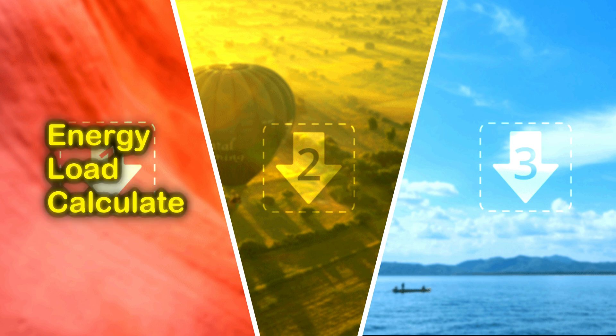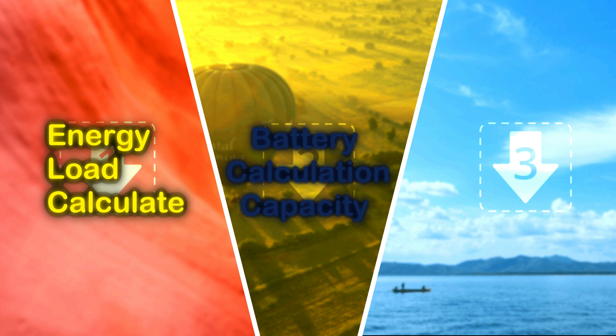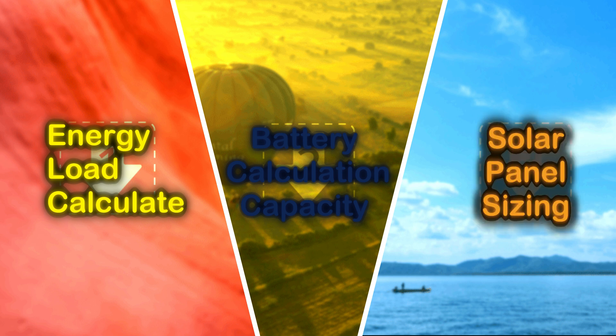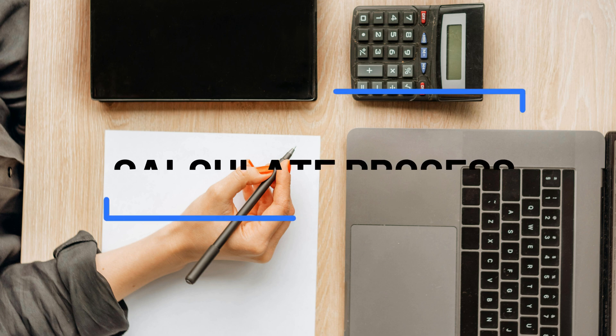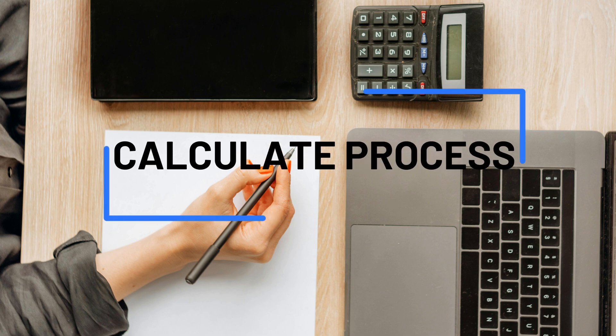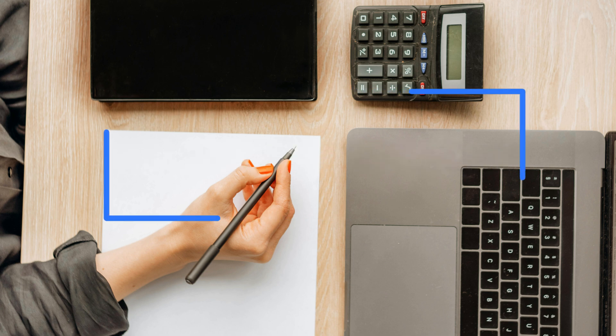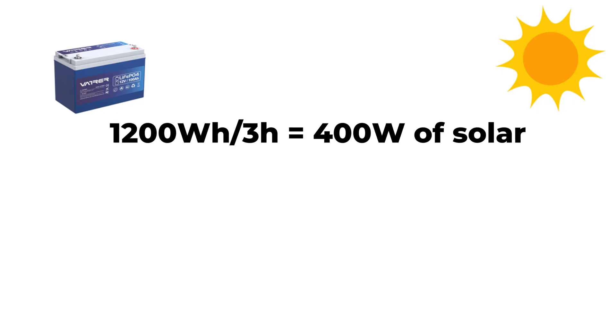First, we need to calculate your load or power usage. Second, is the battery capacity calculation. And third, sizing your solar panels based on your location. Let me give you a simple example: a 1,200 watt-hour battery divided by 3 sun hours requires 400 watts of solar panels to charge that battery.